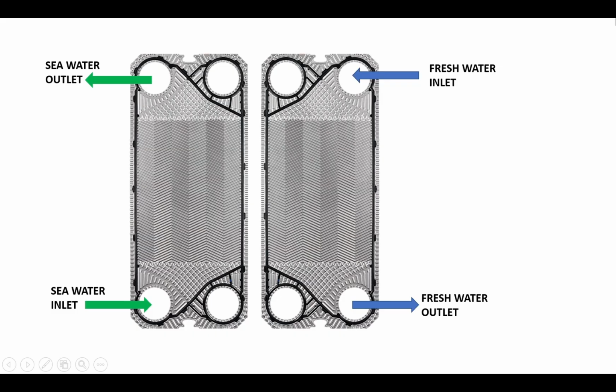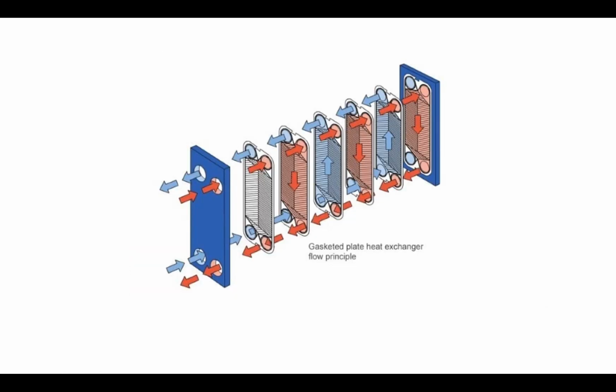Here we have an overview of the plates inside the cooler. Each plate is installed with a rubber gasket to prevent flow of seawater to fresh water and vice versa. On the left plate, the rubber gasket is installed for seawater. Seawater will come from the bottom, pass through the plates, and leave at the top, while the right plate's gasket is installed for fresh water. Fresh water will come from the top, pass through the plate, and leave at the bottom. Here you can see that a series of plates are installed, and each plate is alternately used for seawater and fresh water for efficient heat transfer.